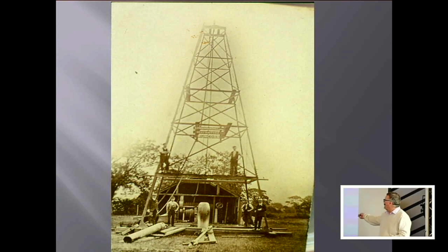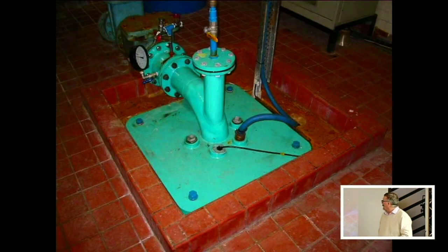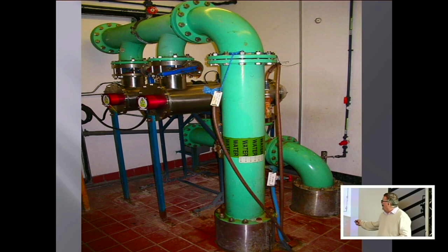And that's what it looked like when they first built it. An actual artesian well, so the ground pressure is actually squeezing the water out of the little borehole. I'm pretty sure it was around about the 1930s. And that's what it looks like today, a little submersible pump right down about 80 or 90 foot. The water pressure brings the rest up in a protective sleeve. It's also disinfected by ultraviolet light. Because the water's very clear, UV light can get in and make sure there are no bacteria or viruses present.